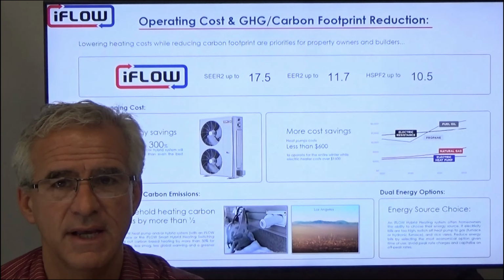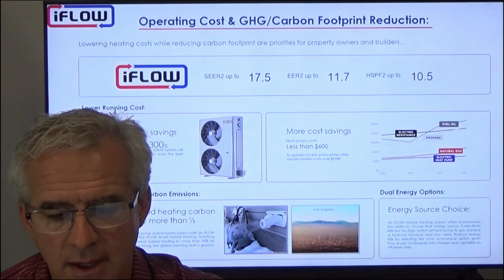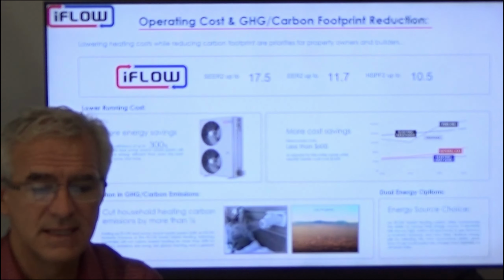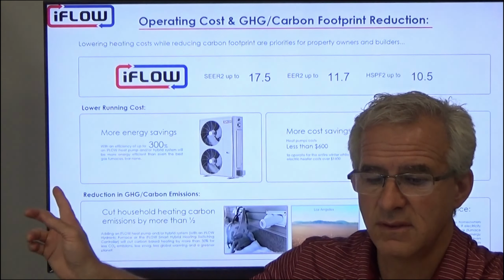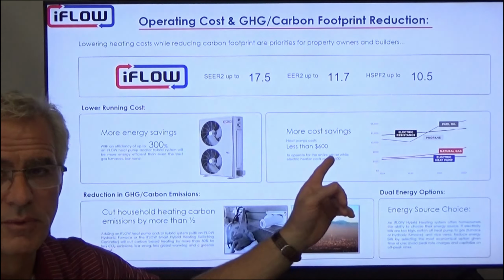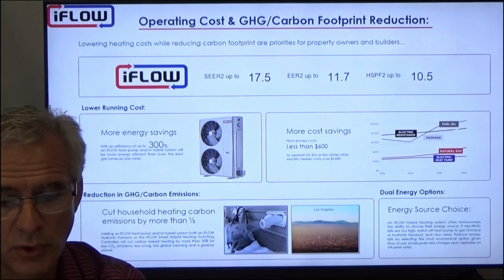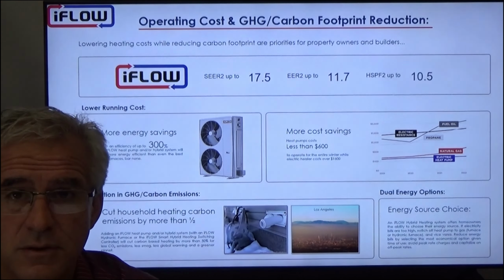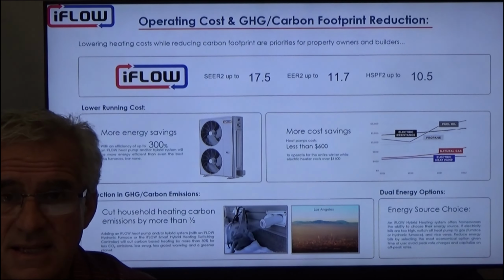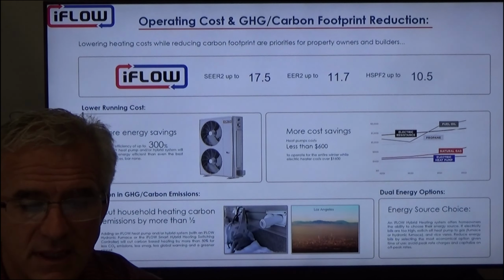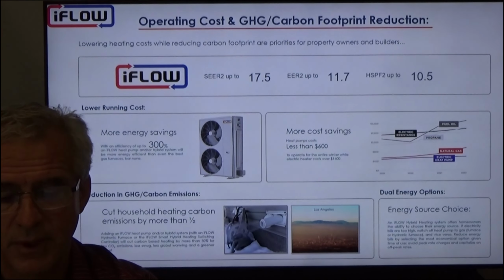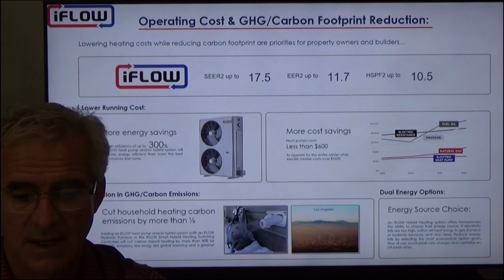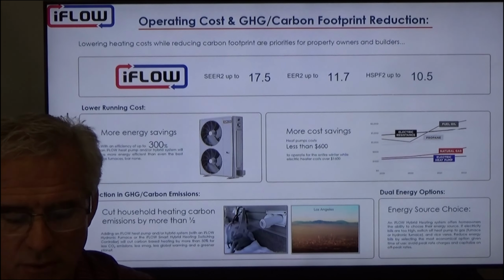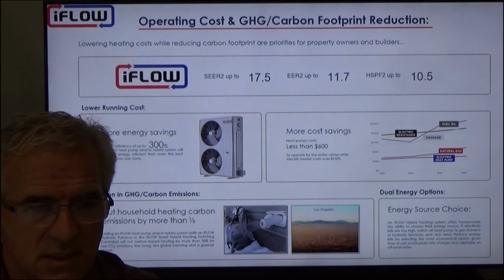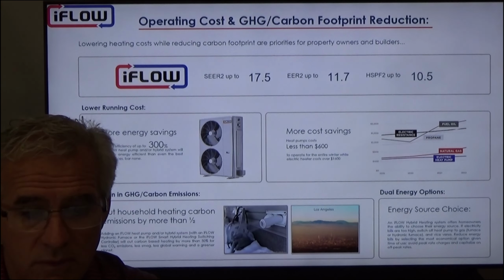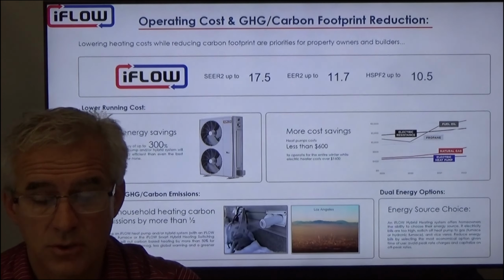We have to offset that with the cost of gas versus the cost of electricity, of course, but we'll look at that. But when we incorporate that into the total heating system, you can see the cost of operation that we have here: fuel oil is quite expensive, propane is quite expensive, electric resistance heating is quite expensive. So really, when we look at the efficiencies of the heat pump in terms of COP and compare that, even with the cost of electricity versus natural gas, they run very close together. So we can create a very economical cost savings option for you that will allow you to choose your fuel.